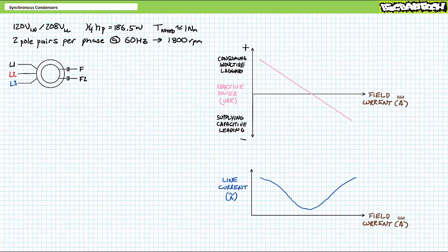By adjusting the magnitude of field current such that the reactive power supplied by the synchronous condenser perfectly counteracts that drawn by the load, reactive power will bounce back and forth at the point of use and the source will stay out of it. Let's see if this is the case.